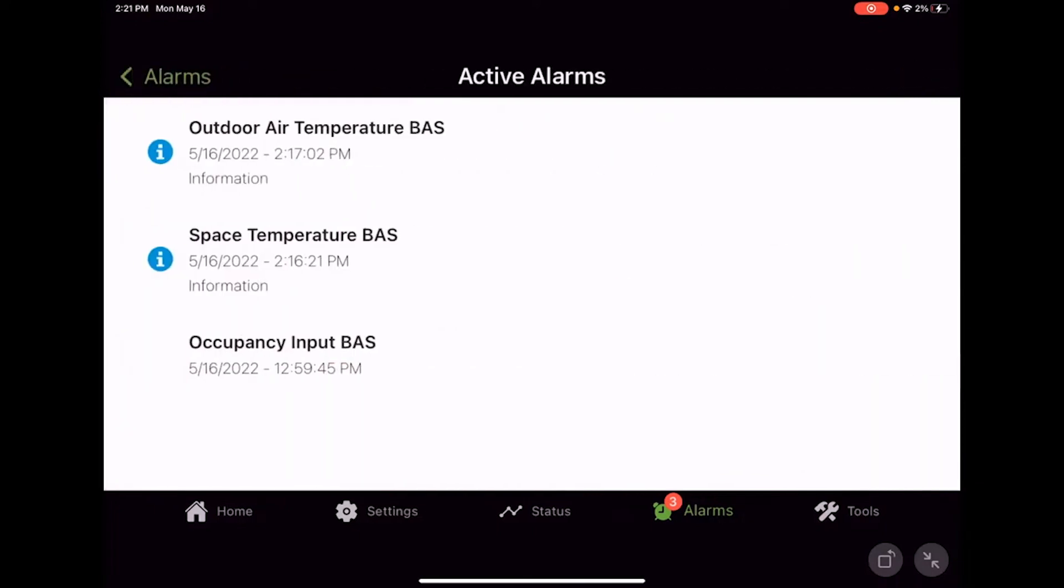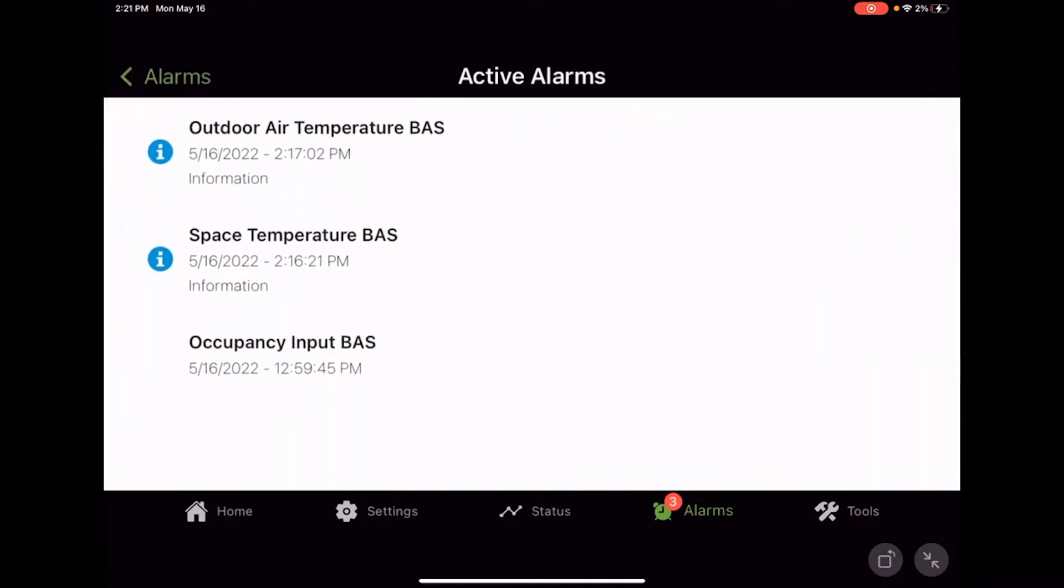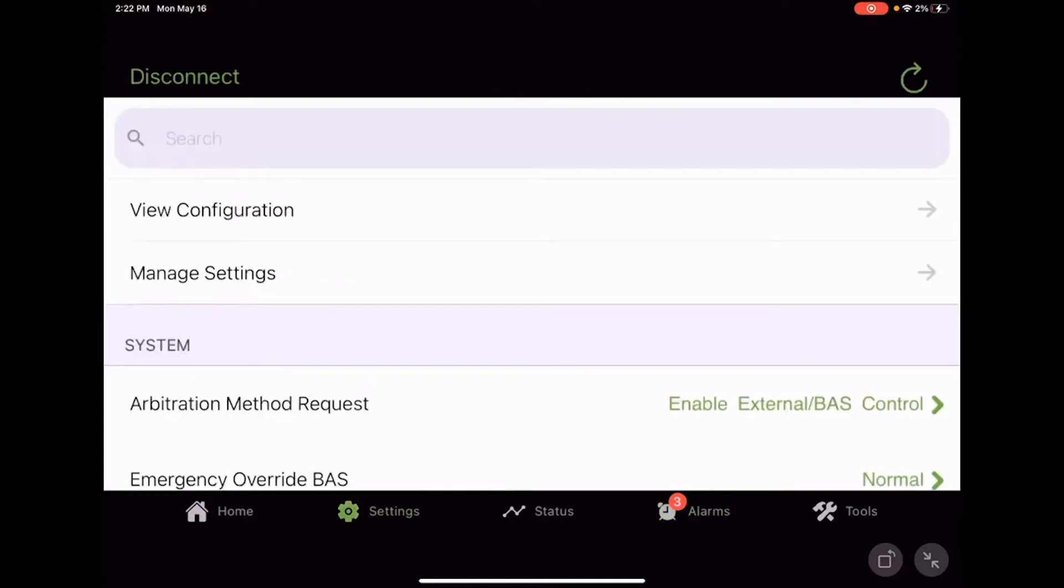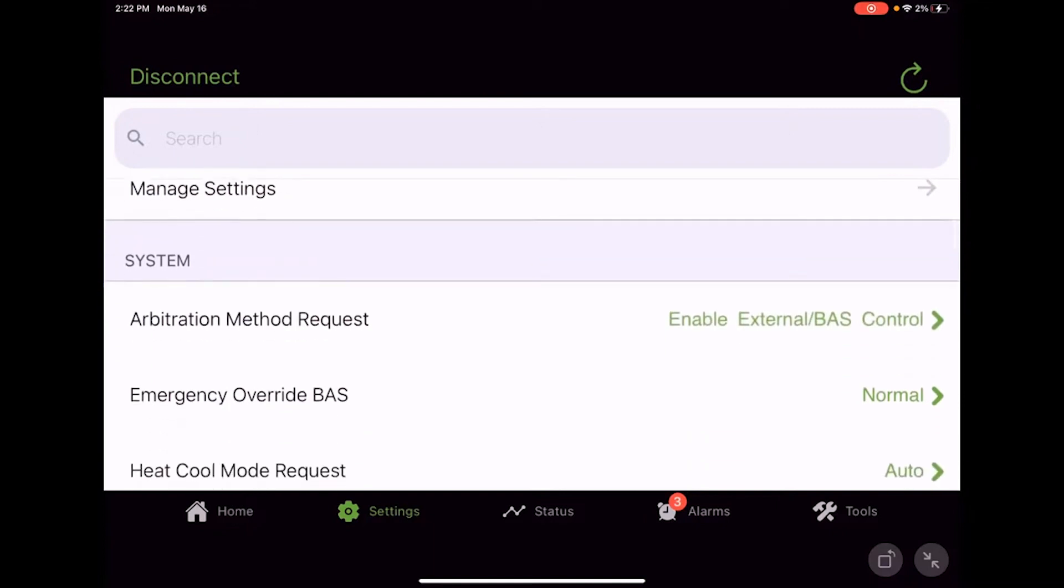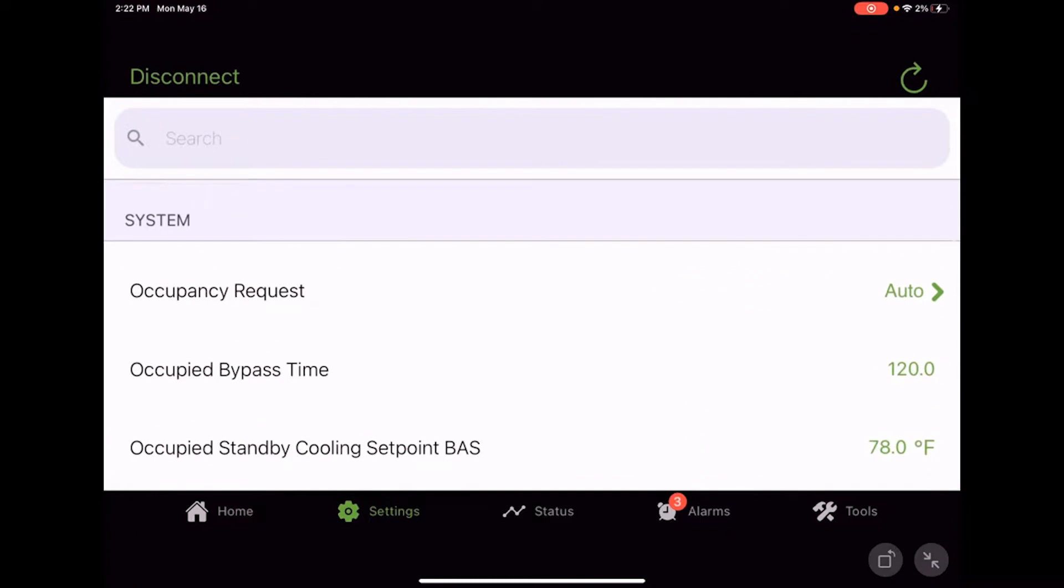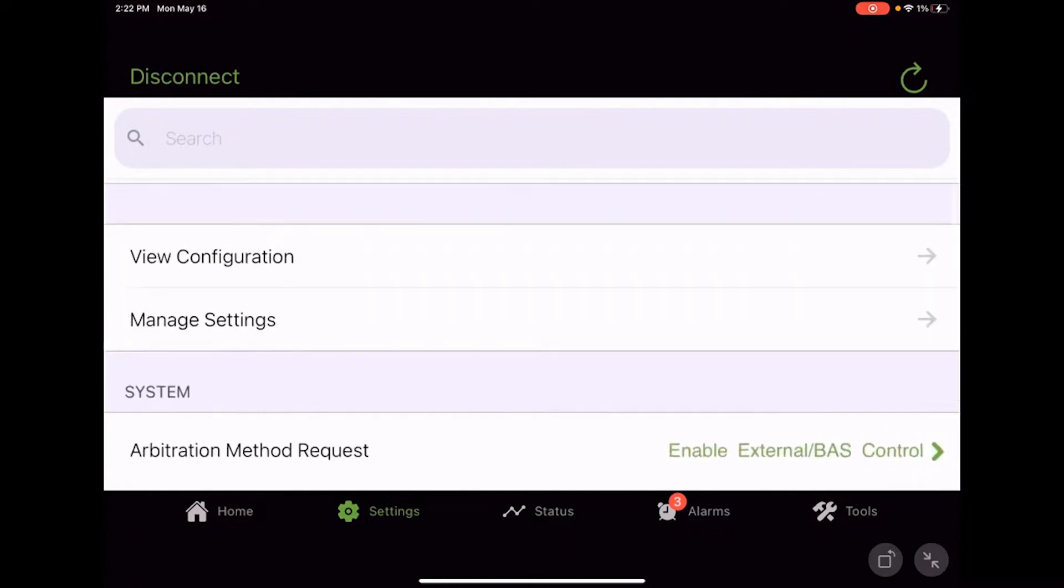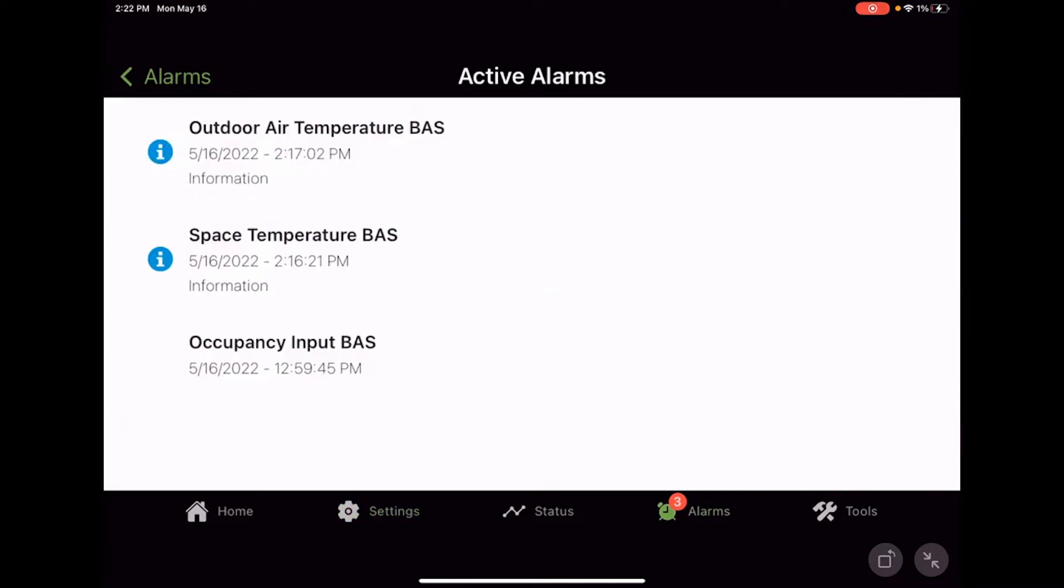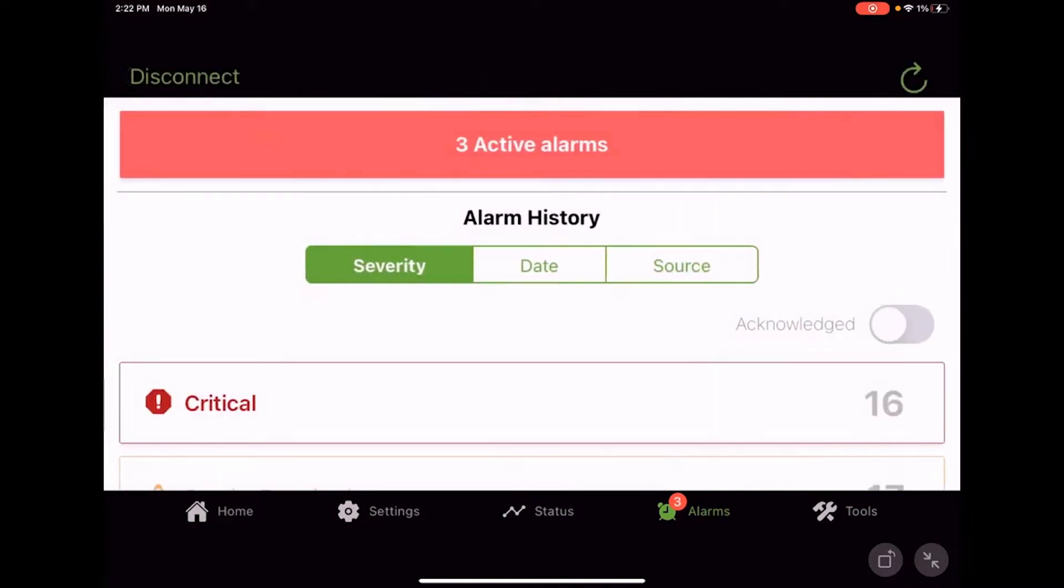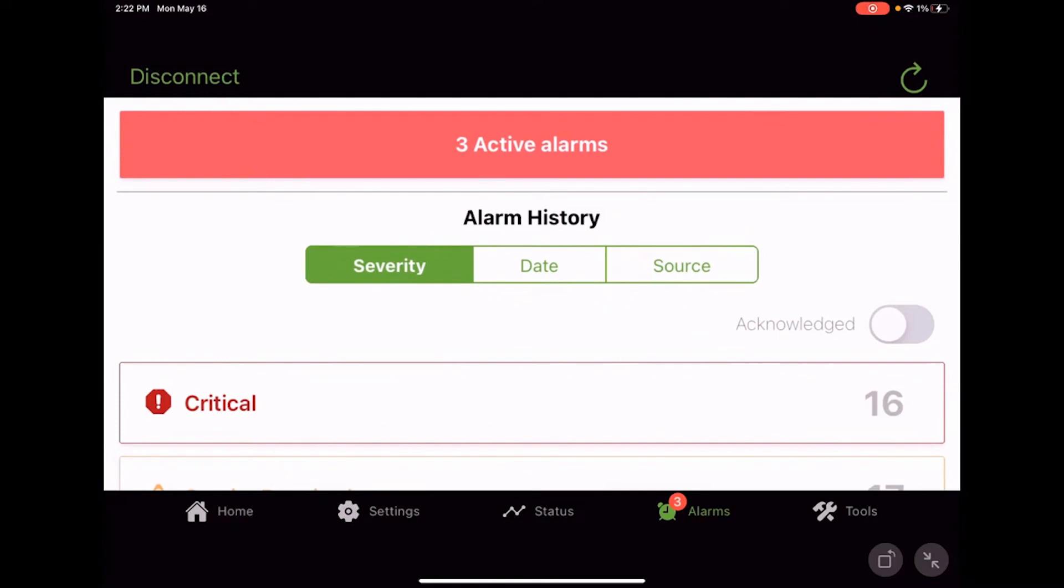Go into active alarms and here we go. We got some outdoor air temp BAS, space temp BAS and occupancy BAS. Well, earlier I went over into settings and I put our unit into BAS control right here. We see the arbitration method request as BAS. So now we've got some BAS values that are coming into the controller and we're using those. And of course it gives us an informational diagnostic that, hey, this information came in and this point went back to normal. So those are some active alarms there.